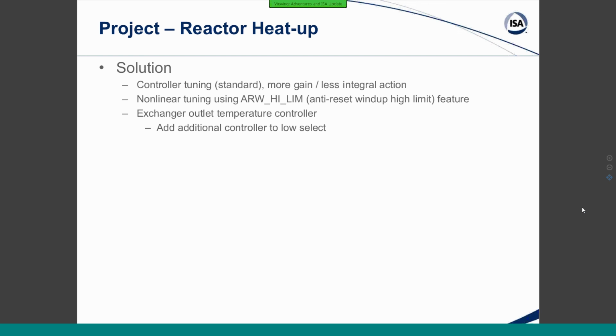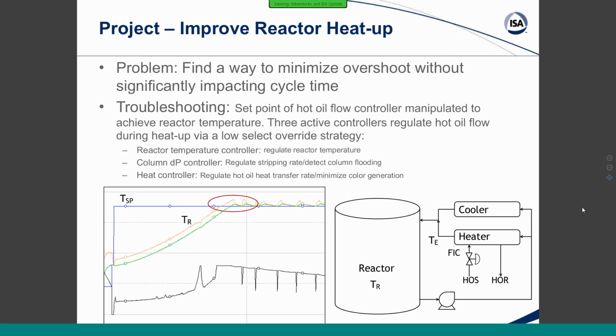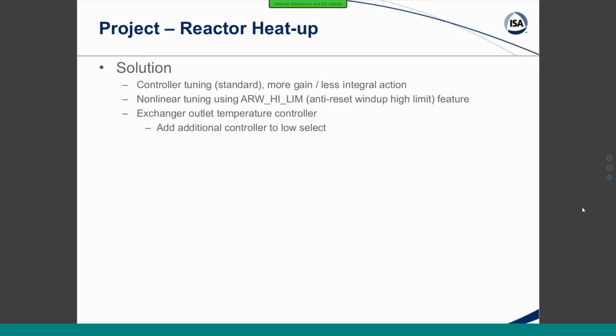So moving forward, we had a couple of different things that we tried and considered. First was just standard controller tuning, increasing the gain. And that just didn't get us the exact results that we needed. You could basically either reduce the overshoot or you could reduce the cycle time. There wasn't a way to get both of them done. We did look at nonlinear tuning using the AntiReset windup limit, and I've got a slide here in just a few minutes that looks a little closer at that. But finally, we settled on the exchanger outlet temperature. We have a temperature on the exit of the heat exchanger, and so instead of looking at the reactor temperature all the time, towards the end of the heat up, when we start getting to that overshoot area, we can actually switch over to a controller looking at the exit temperature, and that gave us a much quicker and more aggressive control action.